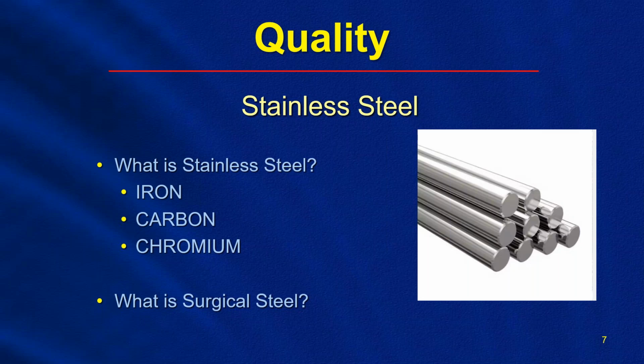Stainless steel is actually a mixture of metals. It's a type of alchemy, if you will, all playing different roles in the final alloy. So the metals found in steel are pure iron, which in and of itself is highly corrosive and soft and will rust very easily. Think of any cast iron pots or pans that you have at home that must be treated to prevent rusting. But when combined with other metals, the iron becomes one of the most commonly used industrial materials. So carbon is added to iron to give it its hardness and ductility. Ductility is what affords the steel the ability to stretch under tensile strength. That's why we see on our needle holders or our clamps, they have the ability to kind of bend and not break when we clamp them down tight. Chromium is added to iron, which adds corrosion resistance. Nickel, manganese, silicon, molybdenum, and sulfur are residual elements and may be present in the composition.